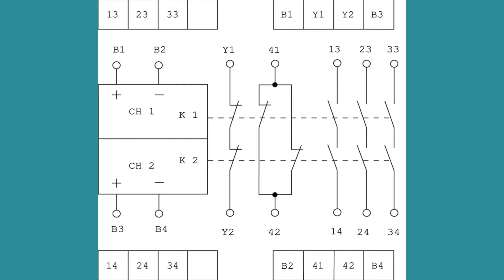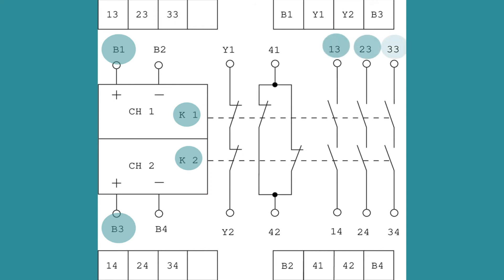We are using the SICK UE10 safety relay. And now you can see the connection diagram. In our scanner we assigned the OSSD safety output and that we will connect to B1 and B3. What will happen is K1 and K2 channels will get energized and we'll get three independent current paths which will be 13, 23, and 33. And these will be your dry contacts to run any equipment that you're trying to stop.